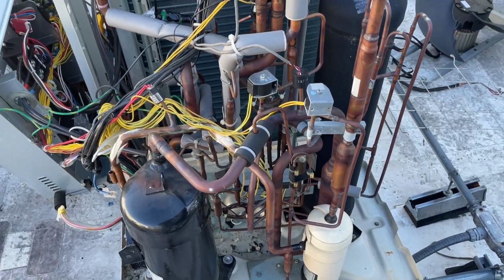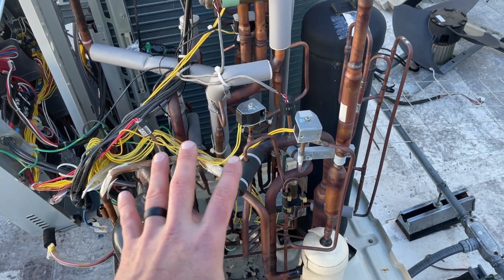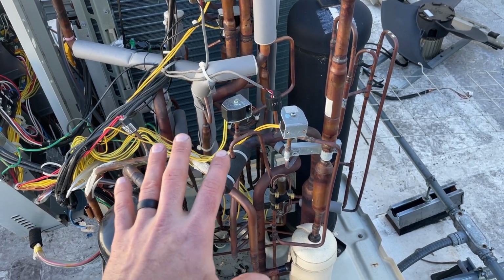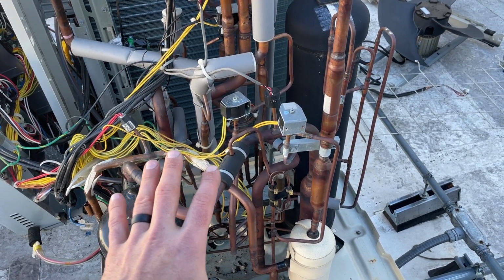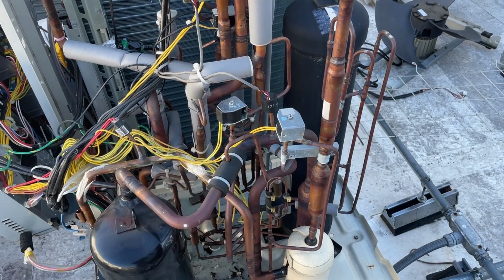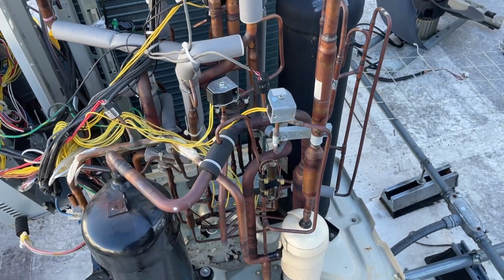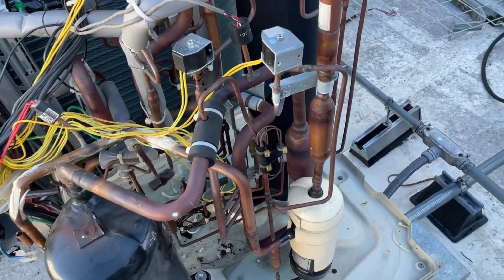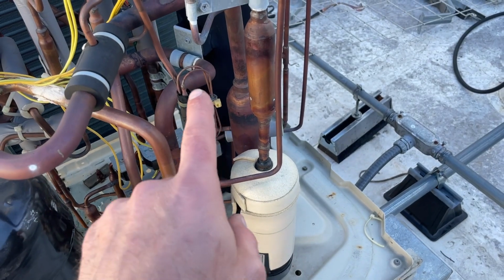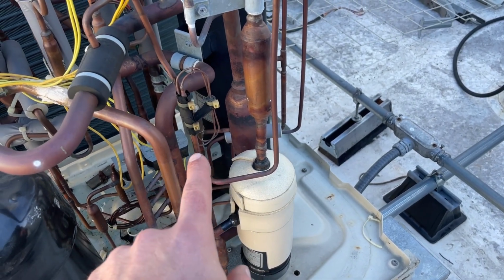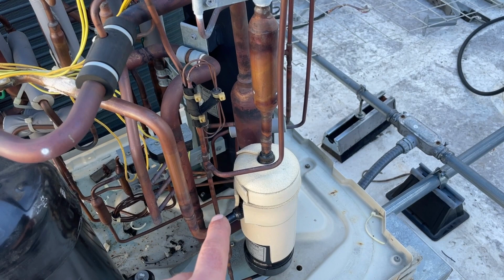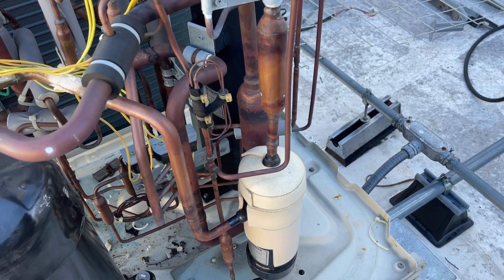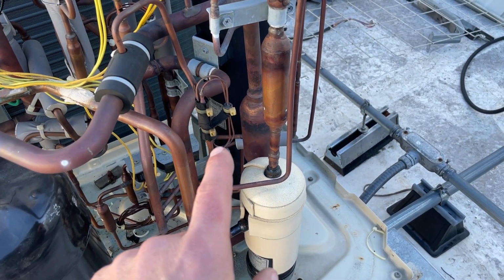To be honest, you have a piping schematic, just like a wiring schematic. That's how intricate and complex all of this tubing is. But if we just want to take a look at a few things, this is an oil return cap tube. These sometimes blow out. They're responsible for a lot of refrigerant loss. They can also get clogged.